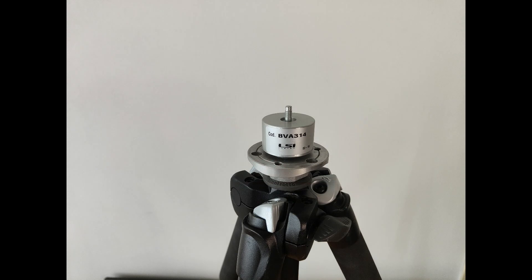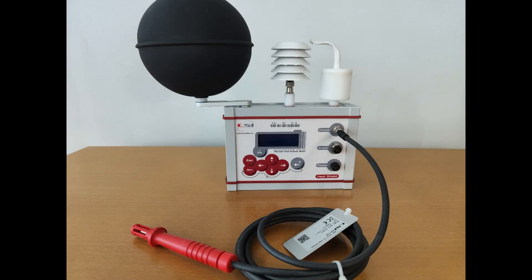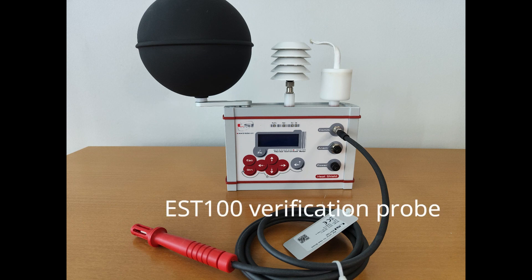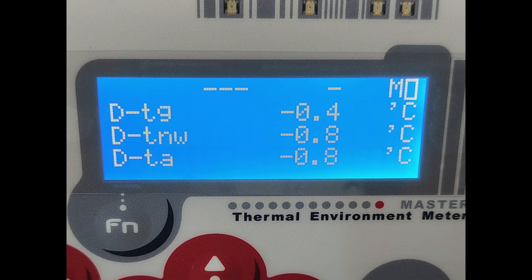Using the BVA314 adapter, for calibration purposes Heat Shield can be connected to the optional EST100 verification probe. This probe is useful to compare measurements from air temperature, globe temperature, and wet temperature with the verification probe's measurements, to check that discrepancies are not larger than the admitted values.